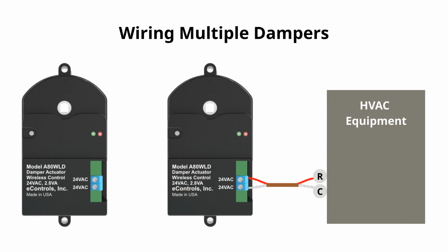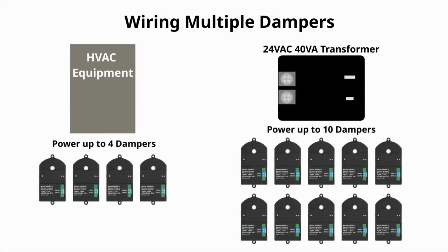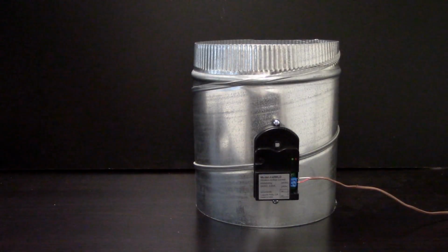If more than one damper is required, you can daisy chain the dampers. The equipment 24 VAC can power up to 4 separate dampers. A 40 VA transformer can power up to 10 separate dampers. Now let's power up the HVAC equipment or transformer. The damper actuator displays a green LED when first powered up. This indicates that the damper is in a fully open position.